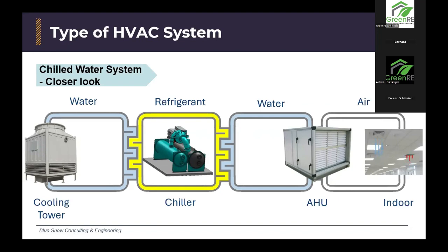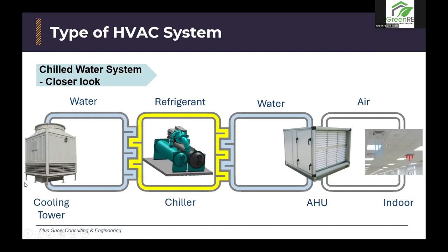So okay, the main thing that you need to focus on here is that there are two closed loop water systems, the first one at the evaporator and the second one at the condenser. But the difference is that the condenser loop is actually an open loop, because there is an opening and it will contact the air. So this one is closed loop. Whatever water stays inside will stay inside. Some debris or dust can still enter the water inside this loop from the cooling tower.